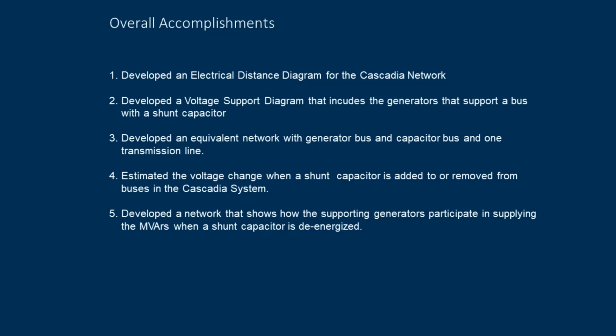From that equivalent network, we were able to accurately estimate the voltage change when a shunt capacitor at Everett was removed from the network, and we verified using Power Simulator that the estimated results agreed very closely with the measured results. We then developed a network that shows how supporting generators participate in supplying the megavars when a shunt capacitor is de-energized. We then compared the results with the power simulator to show that the estimated results agreed very closely with the results obtained with the simulator.